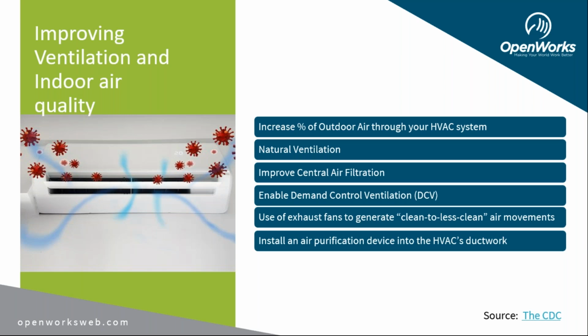We can improve central air filtration. This is accomplished by increasing the MERV rating of air filters installed. You'll want the highest MERV rating filters you can possibly have without significantly diminishing the designed airflow or putting too much static pressure on your HVAC unit. Historically, in commercial buildings, we see MERV ratings of about 7 to 10 for the filters that have been installed. And we're starting to see a push to using MERV 13 filters. They're becoming much more popular and are collecting much more particles and dust.